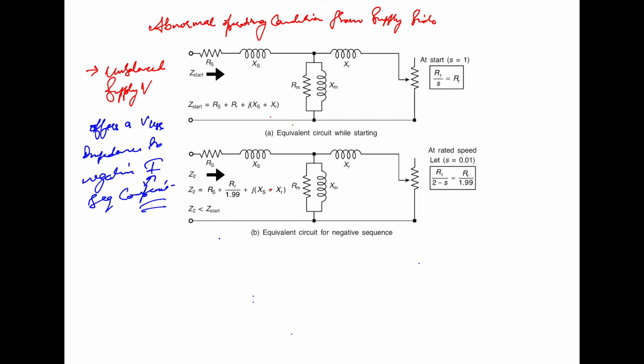In fact, you can say the negative sequence impedance is less than the positive sequence standstill impedance as shown here. In this case you will see a 4% negative sequence supply voltage causes more than 25% negative sequence current to be drawn by the motor.